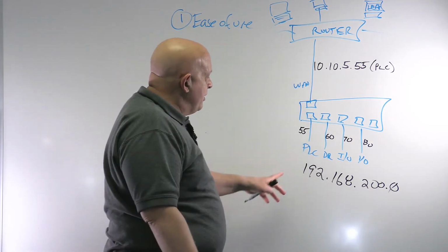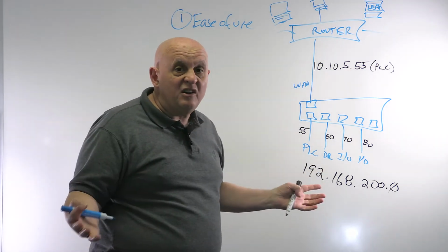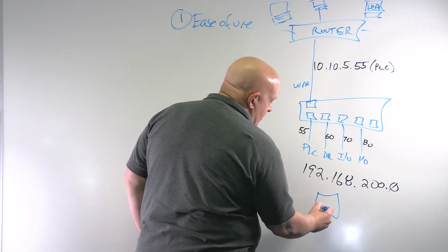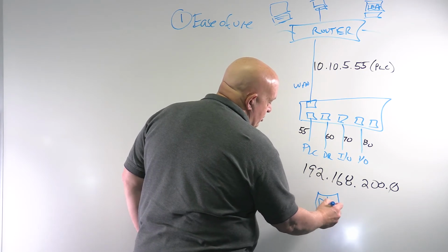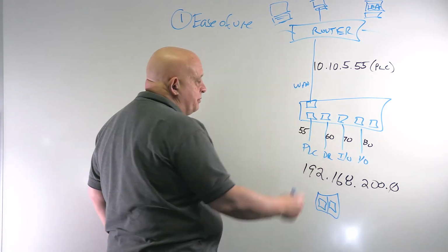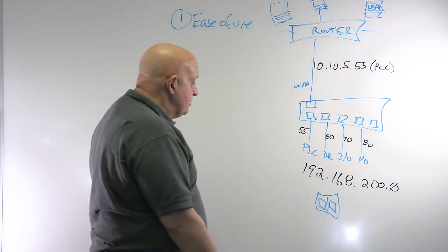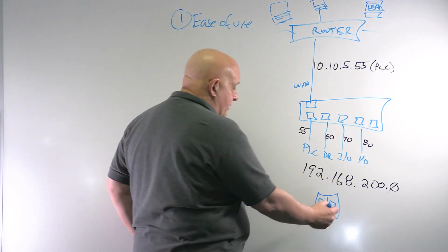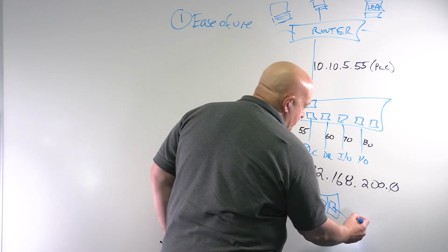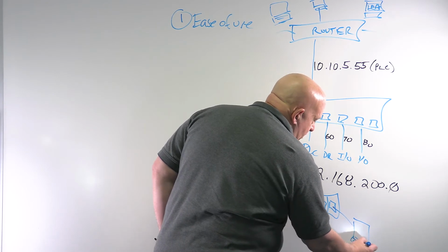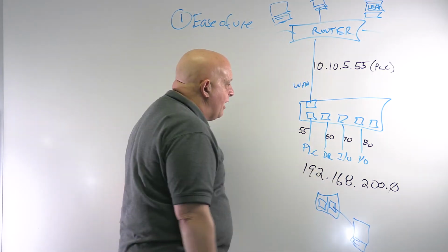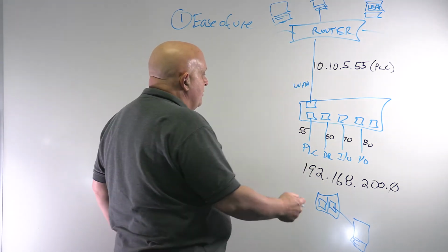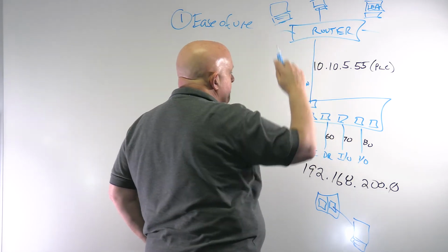Also, lots of times we now have embedded switches. This drive has dual switches, so it has two RJ45 ports, but in this application we're only using one of them. So the robot guy comes in to work on the robot, says, hey, I can hook up to that, and takes his laptop and hooks up to that extra port on the drive. Now he's got access, and he can go up through this switch. It's a switch, so anything can go up that route.